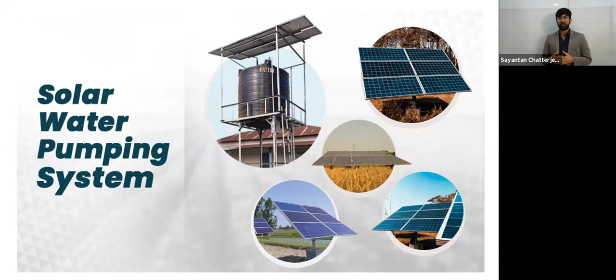Based on the water requirement and water source, we can divide solar pumps into three categories. One is submersible - if we want to extract water from a lower ground level, we have to use a submersible solar pump. If there is sufficient surface water in a pond or lake, we can use surface pumps, but the suction head is only 6 to 7 meters. So if you have a well with a depth more than that, we have to use open well horizontal submersible pumps.